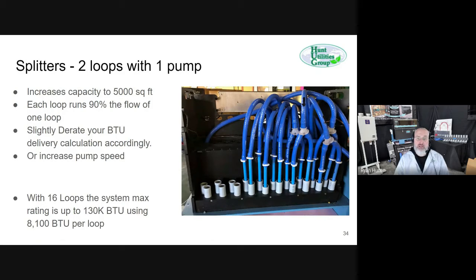There are cases like this one, where the water's coming out and it goes through a splitter. When we specify it, we call it a 2-loop pump, a pump feeding 2 loops. And in that case, each loop gets 90% of the flow that one loop does. It's not a split 50-50 because there's lower resistance. The pump can move more water, and so each loop sees 90%. When I saw that, I was like, man, that's the best bargain ever.